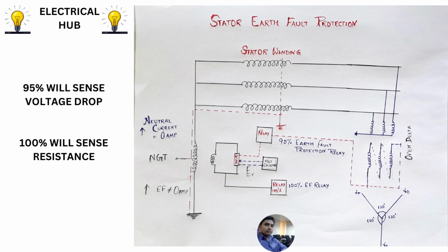So, finally, coming to the conclusion, 95% of the stator winding is protected by a relay which works on the principle of voltage drop, and the remaining 5%, to complete the 100% of the winding protection, is covered by measuring the resistance. So 100% will be protected by using the voltage drop plus the resistance.